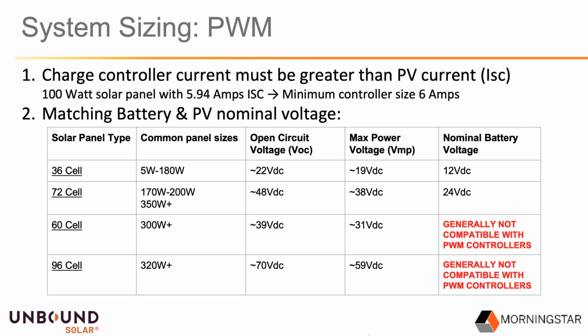30 volts is not enough to charge a flooded lead acid, unless it's cold, in which case you might be okay. If it's a sealed lead acid and you don't equalize, you might be okay. If it's a lithium battery, which charges a little bit lower, you'd probably be okay, or maybe with a higher voltage panel. But that's where the issue comes in: you have a panel that produces just over 30 volts and you're trying to charge at that same range. So if there's any loss from temperature, voltage drop, or other factors that can affect system performance, your voltage won't be high enough to charge.